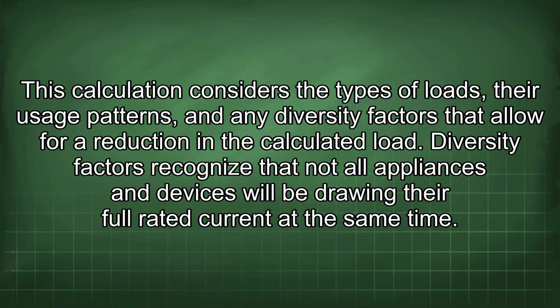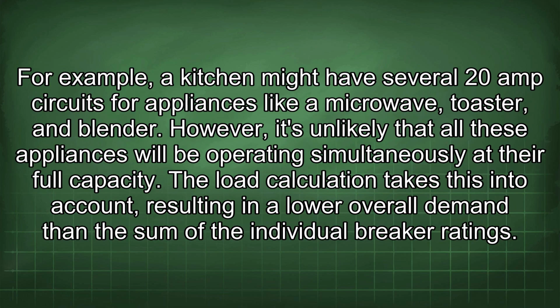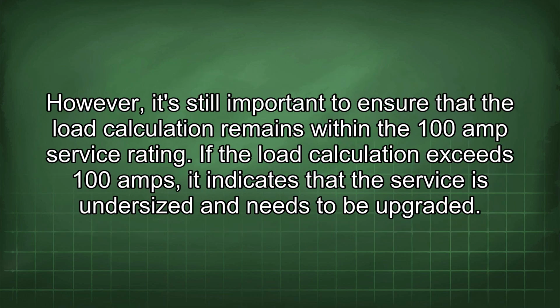This calculation considers the types of loads, their usage patterns, and any diversity factors that allow for a reduction in the calculated load. Diversity factors recognize that not all appliances and devices will be drawing their full rated current at the same time. For example, a kitchen might have several 20 amp circuits for appliances like a microwave, toaster, and blender. However, it's unlikely that all these appliances will be operating simultaneously at their full capacity. The load calculation takes this into account, resulting in a lower overall demand than the sum of the individual breaker ratings. However, it's still important to ensure that the load calculation remains within the 100 amp service rating.